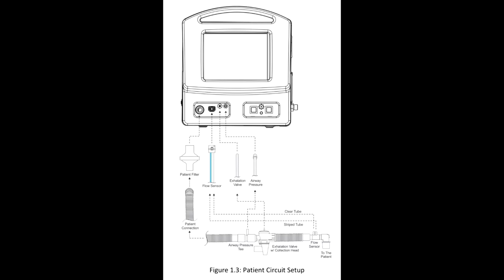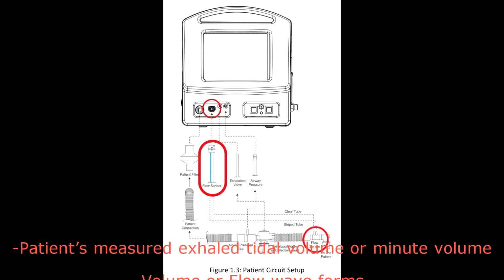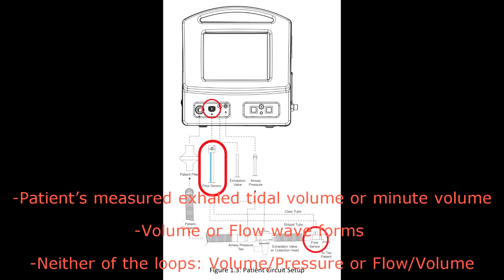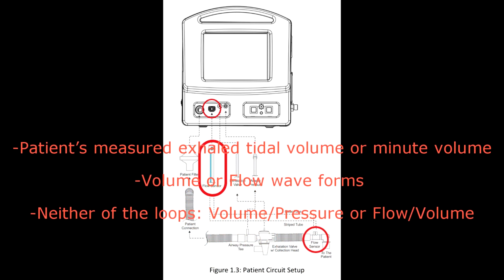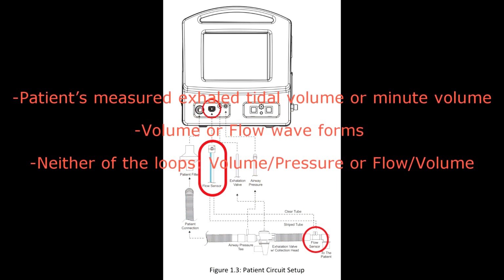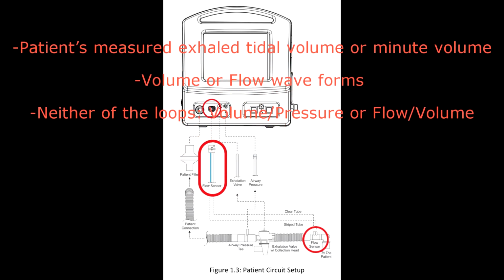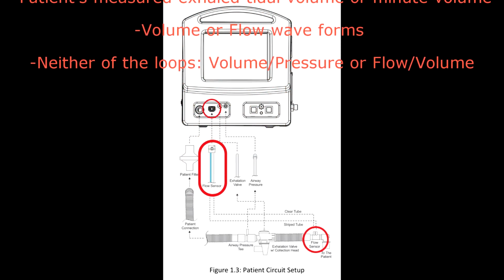Unlike the HT70, each circuit comes with a flow sensor, also known as a pneumotach. The placement of this flow sensor can be seen in this diagram. The vent can be used without a pneumotach, but the following information will not be displayed: the patient's measured exhaled tidal volume or minute volume, the volume or flow waveforms, and neither of the loops, volume/pressure or flow/volume.